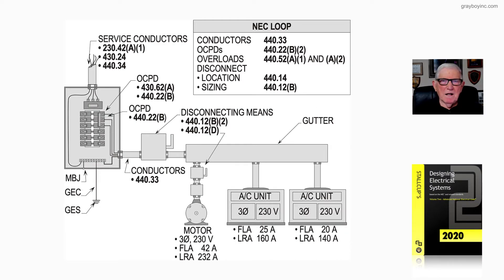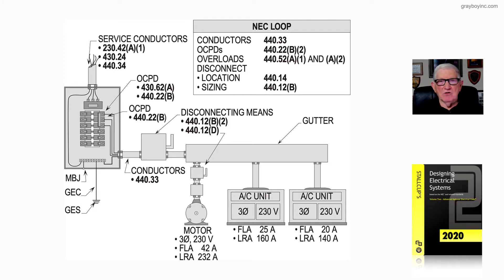Now, this figure 19-6 deals with sizing a disconnecting means, as you see in the illustration, to disconnect one motor and two air-conditioner units. However, it could be two motors, two air-conditioners with other loads, any combination. We did provide you in the illustration the NEC loop, if you wanted to use these sections to size these elements to make up the circuitry of an air-conditioner unit, you could do so. It's a little case study that would be interesting if you wanted to do that.